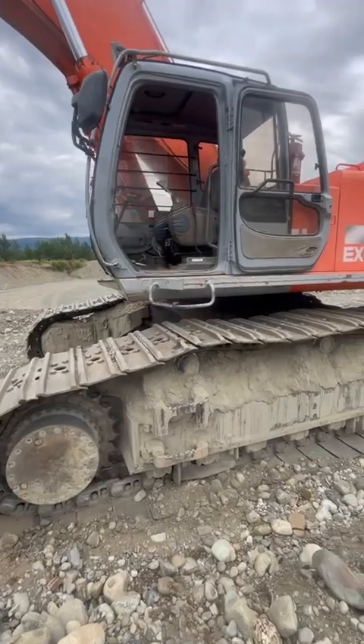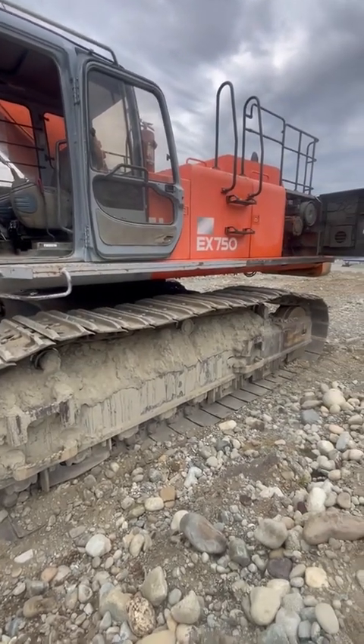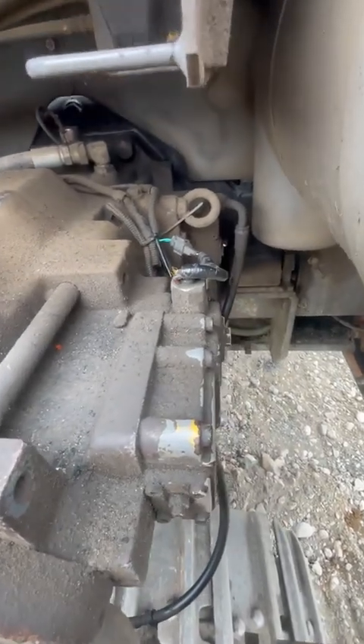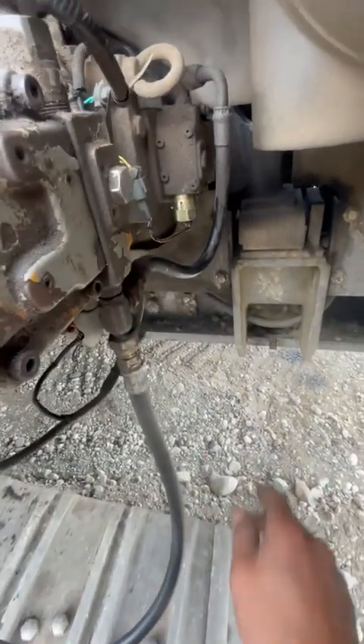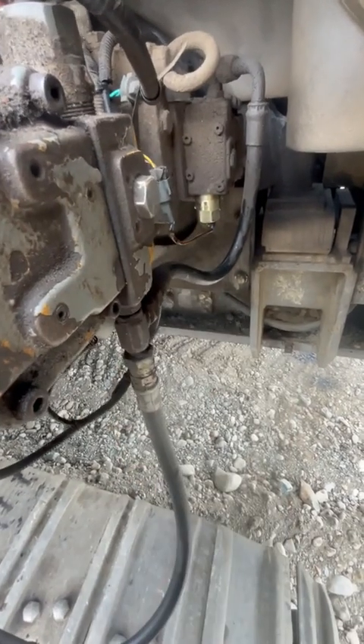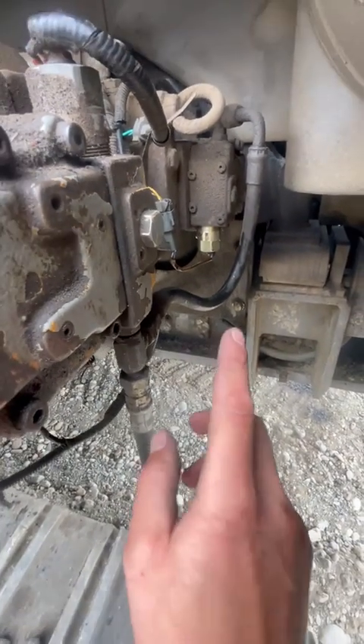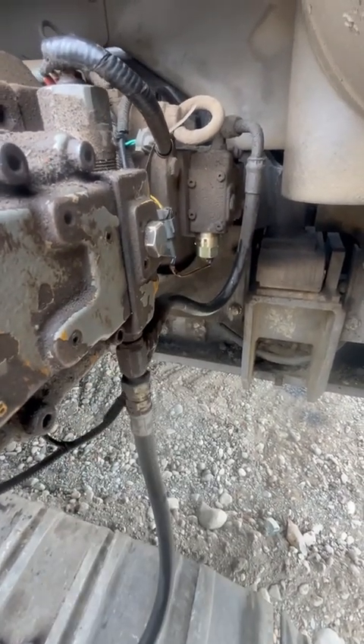All right, we'll do a quick one here on why it's important to load test a circuit or load test wires when you're troubleshooting electrical. So I've got an EX750 here. The customer lost swing function and one of the tracks, and they found a broken wire on that pump control solenoid. They replaced that, but it didn't fix the problem.